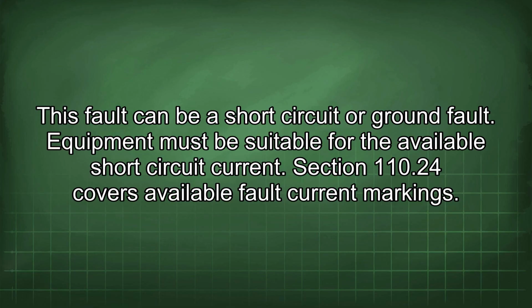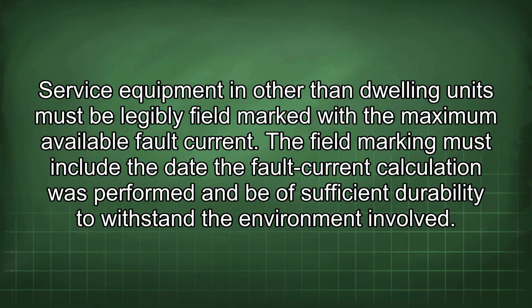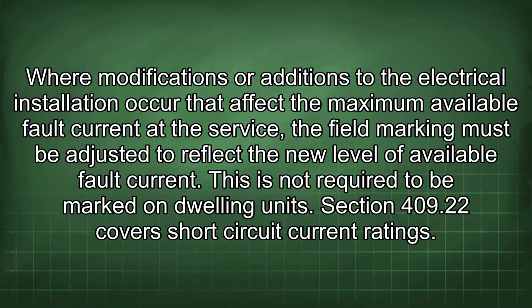Section 110.24 covers available fault current markings. Service equipment in other than dwelling units must be legibly field marked with the maximum available fault current. The field marking must include the date the fault current calculation was performed and be of sufficient durability to withstand the environment involved. Where modifications or additions to the electrical installation occur that affect the maximum available fault current at the service, the field marking must be adjusted to reflect the new level of available fault current. This is not required to be marked on dwelling units.